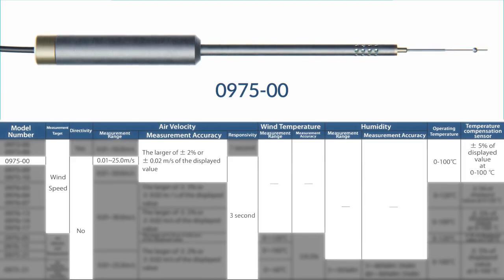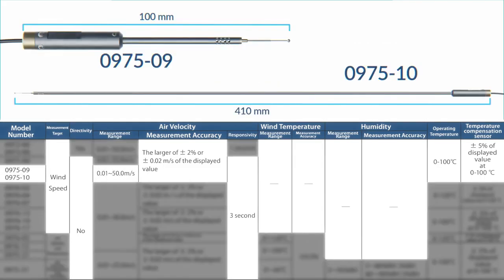Its needle-type form factor is great for measuring turbulent airflow in a circular plane surrounding the sensor, and a very good response time to changes in temperature is required. Models 0975-09 and 0975-10 are omnidirectional probes that measure air velocity within a range of 0.01 to 50.0 meters per second. They're accurate to the larger of plus minus 2% or plus minus 0.02 meters per second of the displayed value, processed every 3 seconds, and operate at temperatures from 0 to 100 degrees Celsius. 0975-09 is identical in form factor to model 0975-00, but, as mentioned, measures in a wider range. So, it can be used in similar applications that operate with higher air velocity.